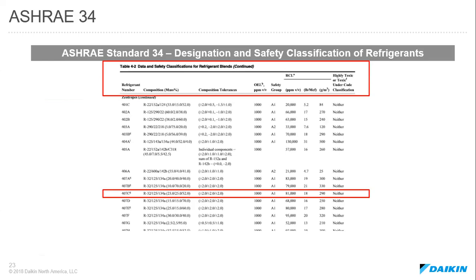So if I were to take a snapshot of this code, this is what it looks like. It gives us a long list of hundreds of different refrigerants that have been developed. A lot of these refrigerants that we utilize today, such as R407C, which I've highlighted here, and R410A, are actually zeotropes, which means that they're blends of refrigerants. And so as a refrigerant is developed, ASHRAE 34 helps us figure out what safety group, what allowable level in parts per million, is allowed for that refrigerant to be in the space. It helps us figure out if that refrigerant is flammable or toxic, and tells us what refrigerant concentration level is allowed.